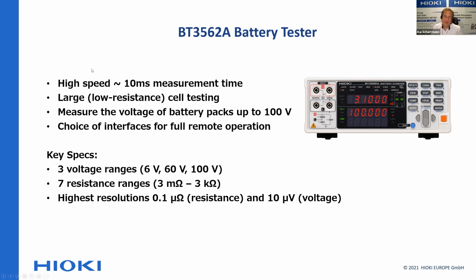So the nice thing about the BT3562 is it's a very fast measurement - it measures within 10 milliseconds. It's ideal for large, low resistance cell testing because it has a 3 milliohm range. It has 7 resistance ranges, and the voltage range of the BT3562 is 6 volts, 60 volts, 100 volts.